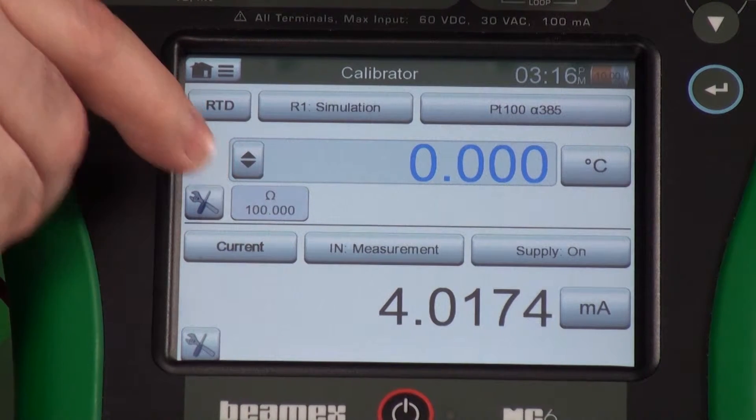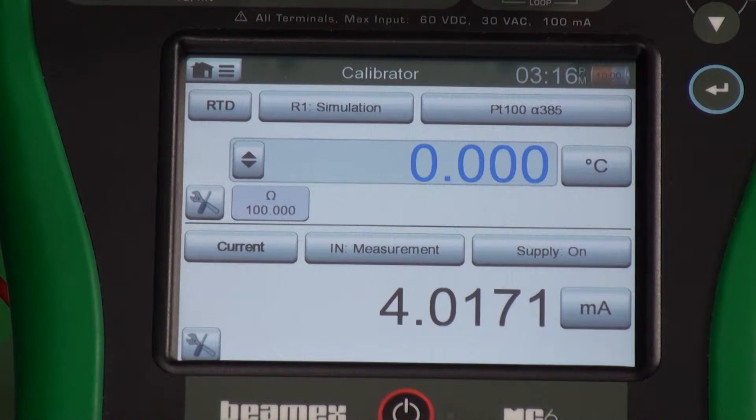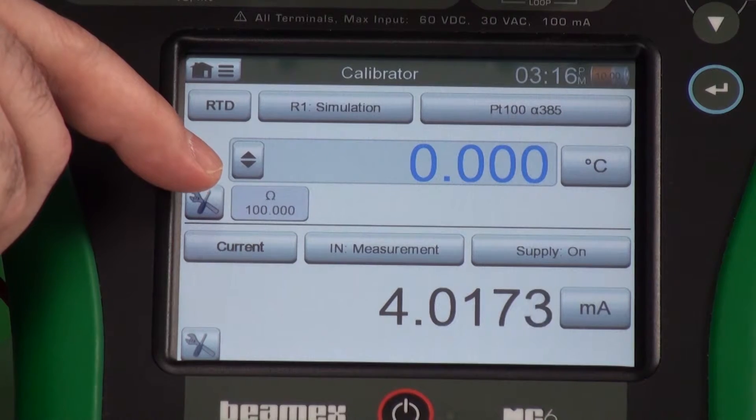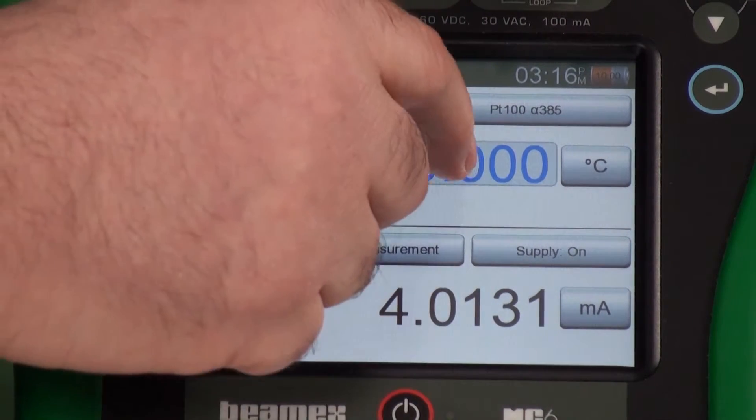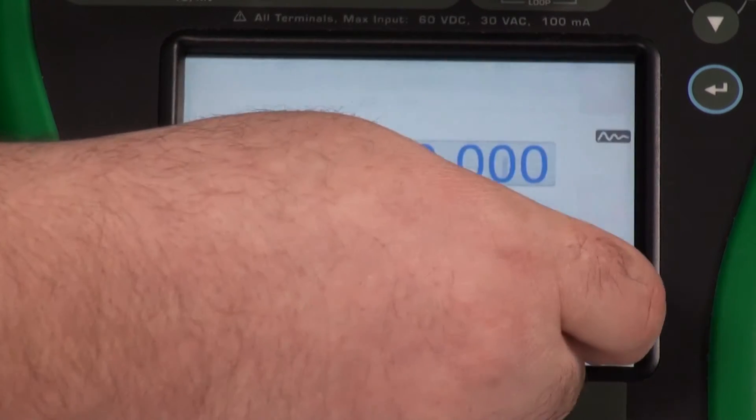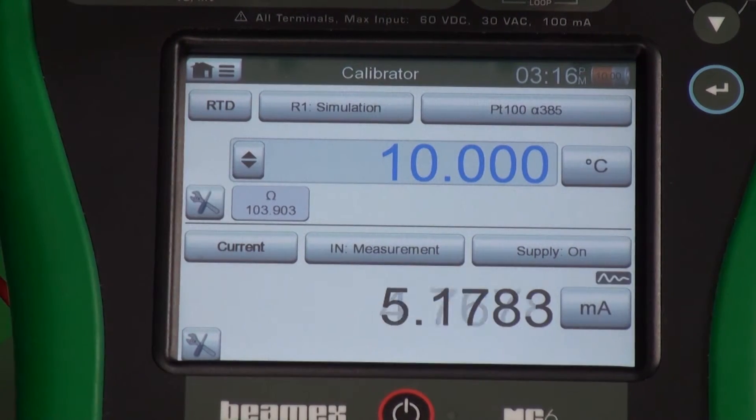On here, the definition of a Platinum 100 385 is that you get what resistance at zero degrees Celsius? You get 100. So we're showing that we're actually simulating 100 ohms into this. Let's change the value. Maybe I want 10 degrees. My resistance has changed.